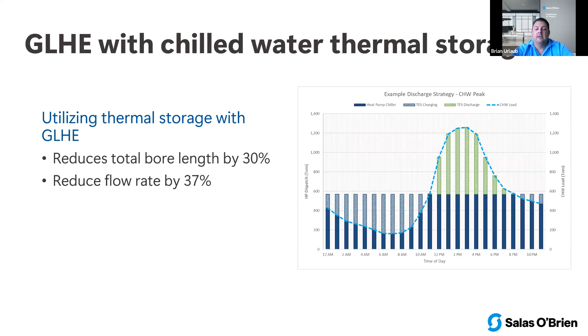Most of these campuses have heating and cooling happening year round between reheat, domestic hot water, and even in the middle of winter, most of these campuses with labs and so forth have some chilled water and cooling in interior spaces. So they're running in simultaneous mode almost all year round in these large campuses where we've got central plants.